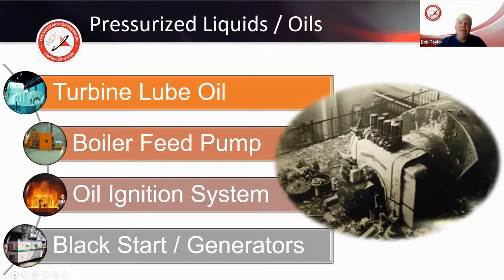In typical plants, they're used for the turbine lube oil. The boiler feed pump has a lube oil system, and both of these systems have a large reservoir. Typically, those reservoirs of lubricating oil are somewhere near the actual process equipment. There's piping transferring the liquid to the process equipment for its lubrication or for its cooling. Some plants use oil, and pipe it into the boiler to establish a fire and heat the boiler so that when the coal is delivered initially, it ignites the coal and sustains a flame there. So they may have an oil ignition system.